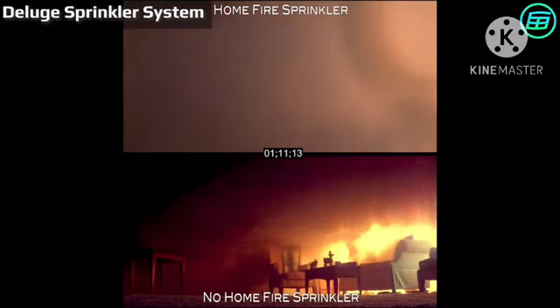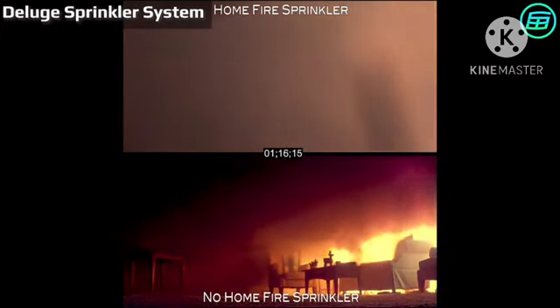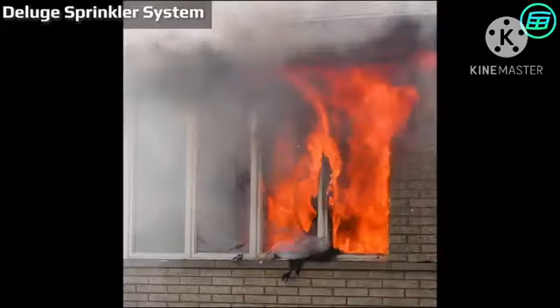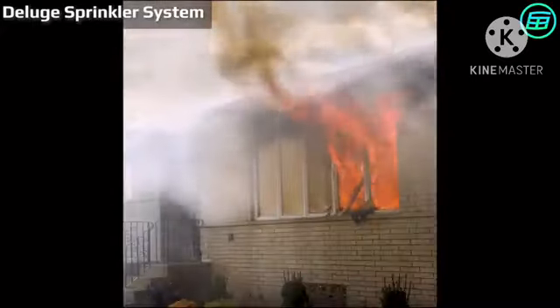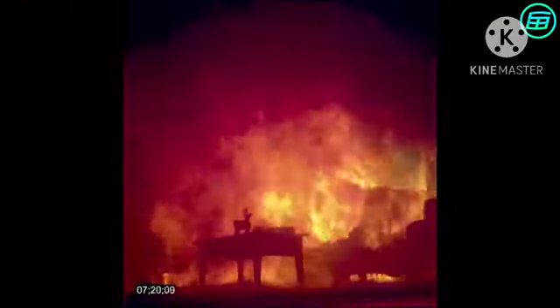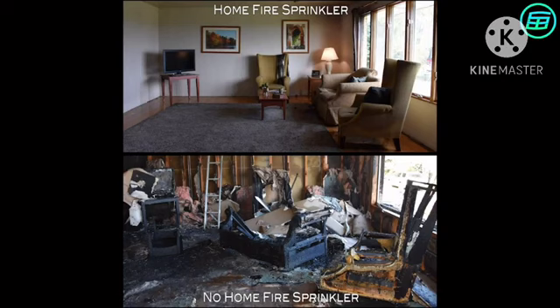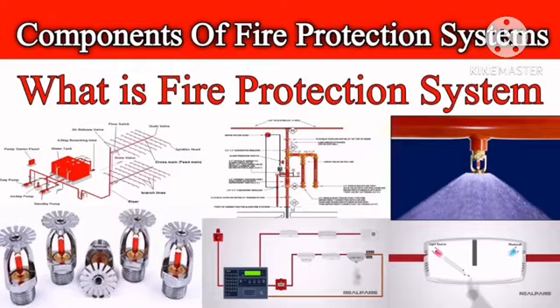However, in this system the sprinkler heads are always open. The sprinkler heads don't have heat sensing elements but instead are activated by external smoke or heat sensors. Once heat is detected, water fills the pipes and is released to all open sprinkler heads, creating a flooding effect across the entire area. This system is most often used in industries with flammable liquids, which pose the threat of rapidly spreading fire.